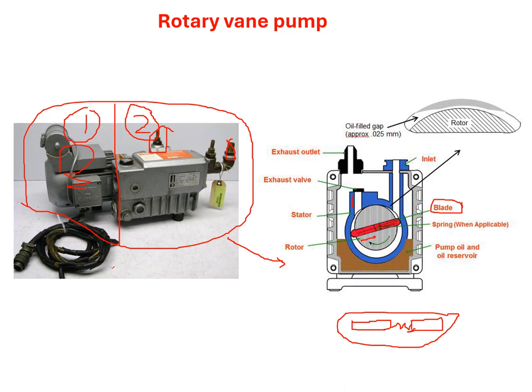At the bottom we have the pump oil and oil reservoir. This is the inlet from where all the gases from the chambers go inside this pump — they are sucked by this pump from the chamber, which may be connected here where we want to grow the thin films. We also have an exhaust valve and exhaust outlet, so whatever gases are sucked from the chamber will actually go out through this.